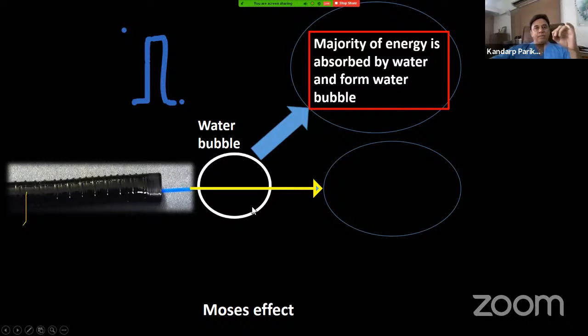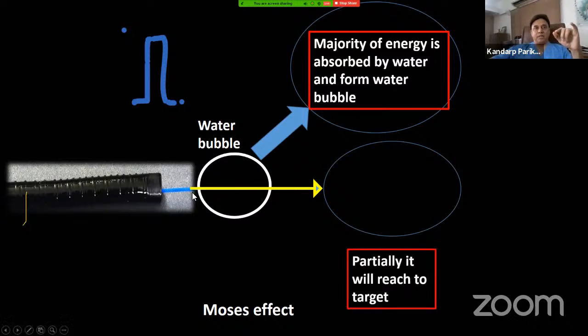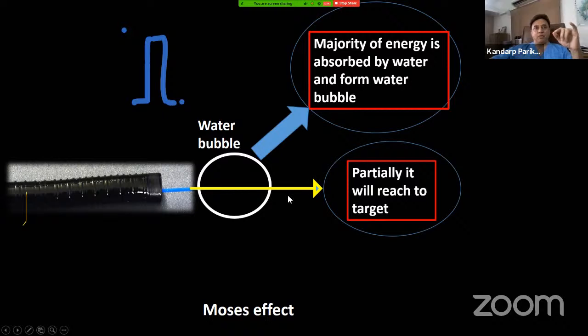The bubble which is formed by this holmium YAG laser, what we use, is a small size. So before it bursts, some amount of the energy passes through that vapor channel and goes to the target, that is the stone. So there is great energy loss. Secondly, the bubble which forms, they burst and they produce acoustic. So this photoacoustic effect can also push the stone slightly back. So there is a retropulsion, but this photoacoustic effect is comparatively less.